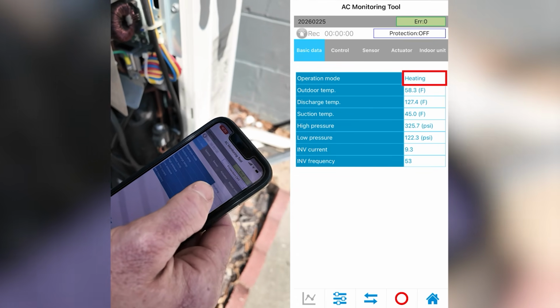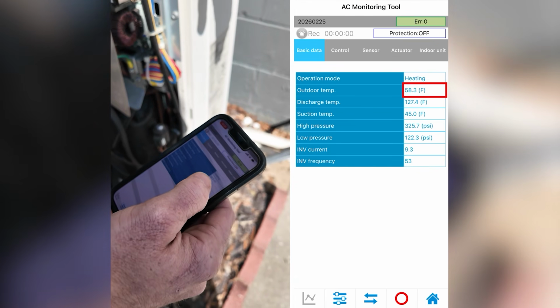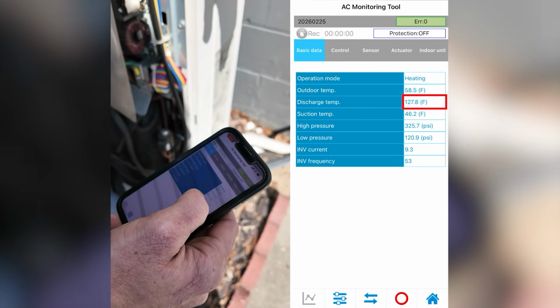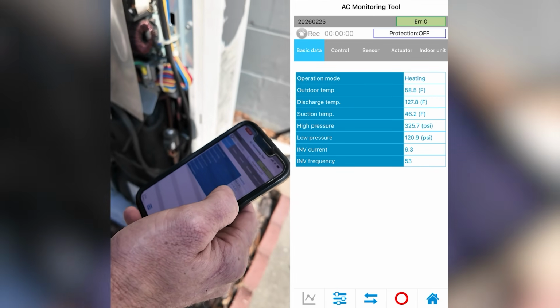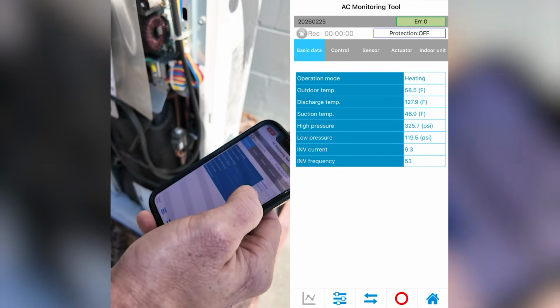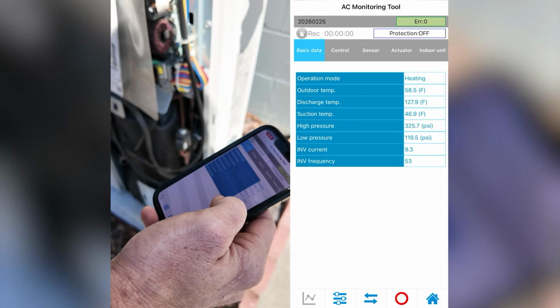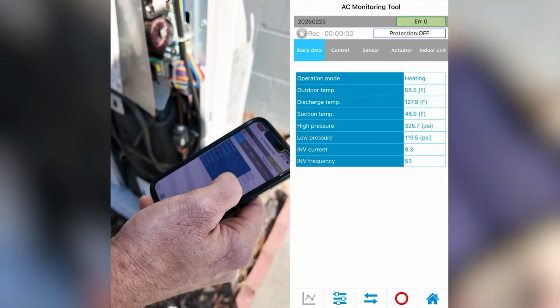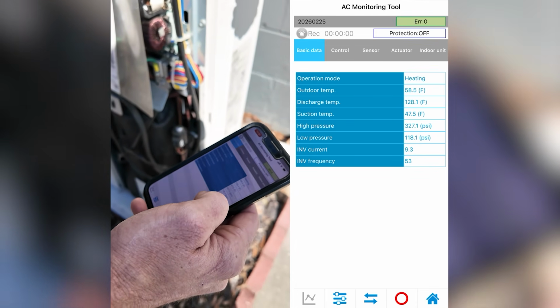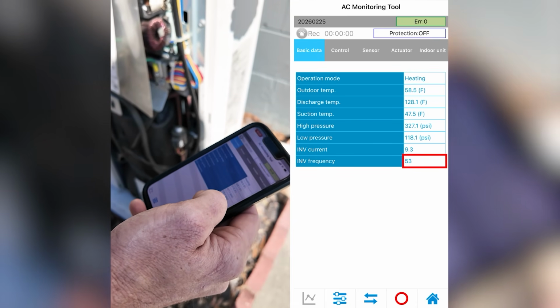So the system is in heating mode. It has an outdoor temperature of 58 degrees, discharge temperature is 127, suction temp. This is where you're going to go through and look at the mapping to make sure that everything in each category makes sense, right? That my PSI is not in my discharge temperature range. Maybe I accidentally clicked the wrong model. My compressor frequency is at 53.